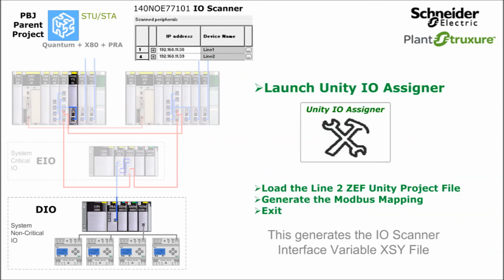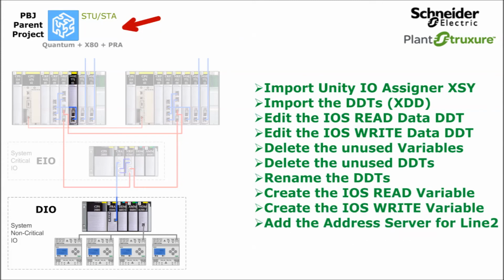Next, launch the Unity IO assigner and load the line 2 ZEF file. Then generate the Modbus mapping and exit. This will generate the IO scanner interface variable XSY file. Then repeat the steps previously carried out in the parent Quantum project to complete the line 2 IO scanner interface.